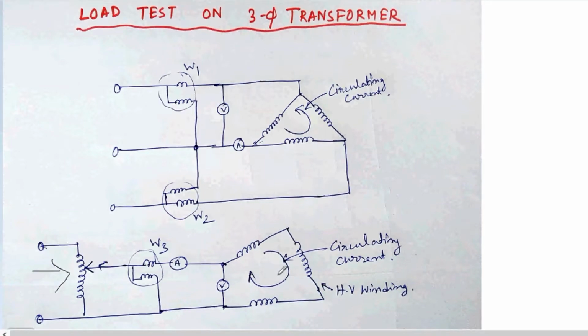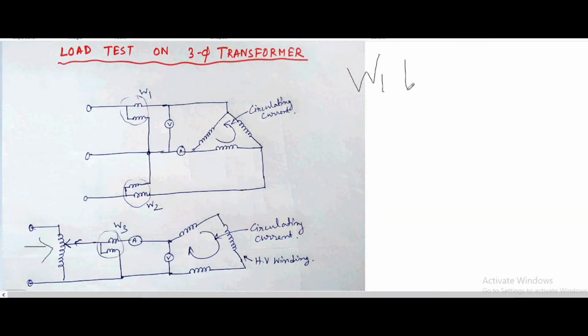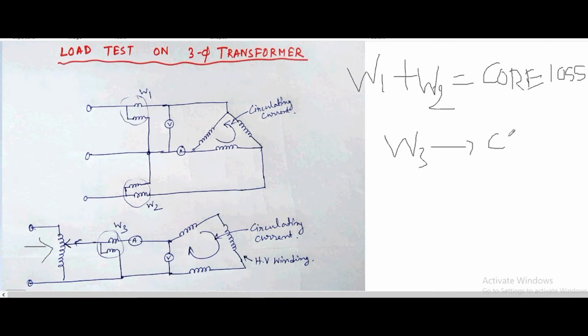At the same instant, the primary will circulate the rated current, and here the wattmeters W1 and W2, W1 plus W2, will give us the core loss. So this is the core loss, whereas the W3 wattmeter will give the copper loss. W3 will give us the copper loss.